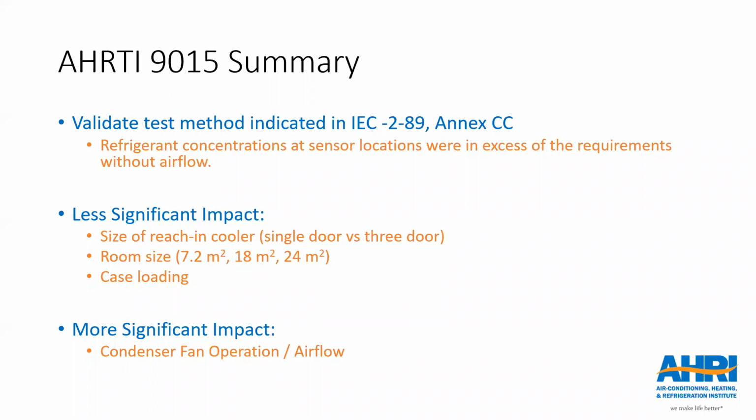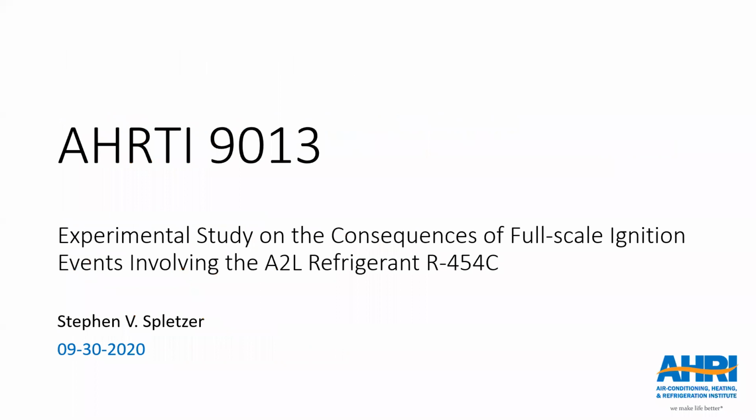Mark, thank you for the great presentation here. And I just want to interject one point about the external release tests and the refrigerant leak rate in the testing. We actually determined the leak rate using the standard 2-89 defined formula. And so for a specific charge level, we tested one leak rate. To that point, I want to introduce another RD project, which actually tested three levels of leak rate for a specific charge level to basically simulate large and medium and small leaks and so on.